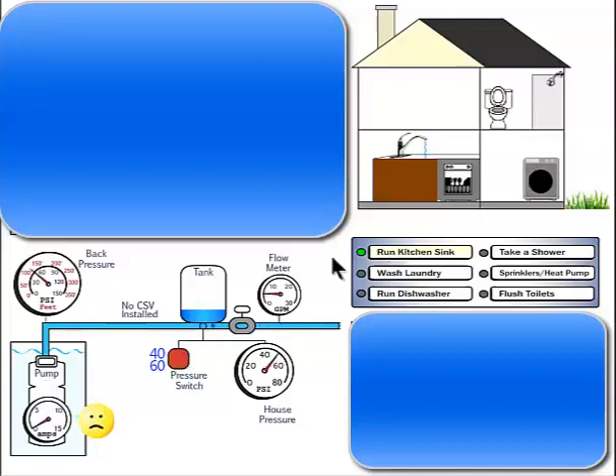With the 5 gallon per minute faucet still running, the water in the tank is quickly depleted and the pump is cycled on again. Small flow rates will cause the tank to fill quickly and drain slowly. Opening additional taps or larger flow rates will cause the tank to fill slowly and drain quickly. Either way, the pump continues to cycle on and off while water is being used.